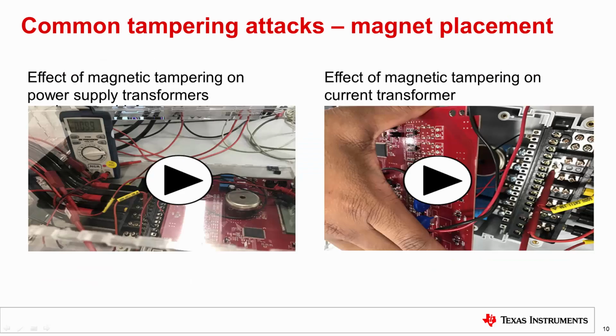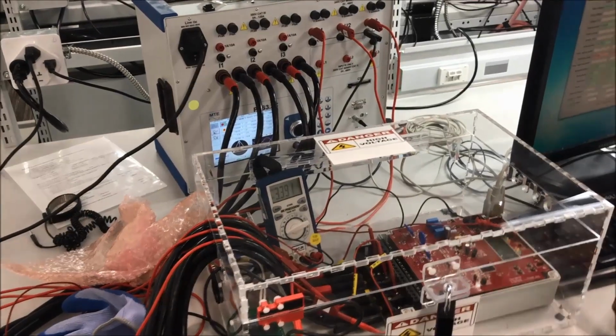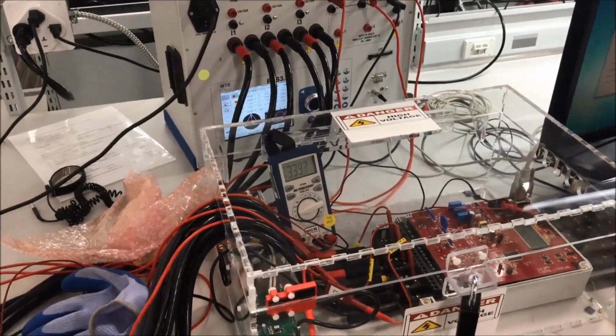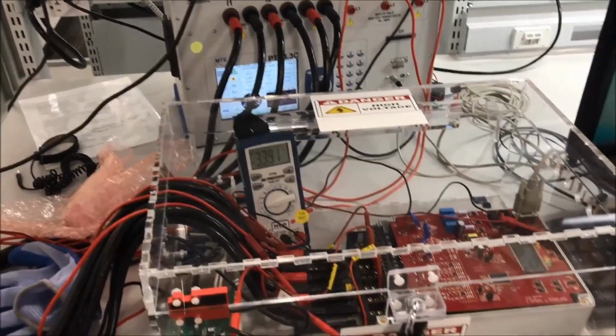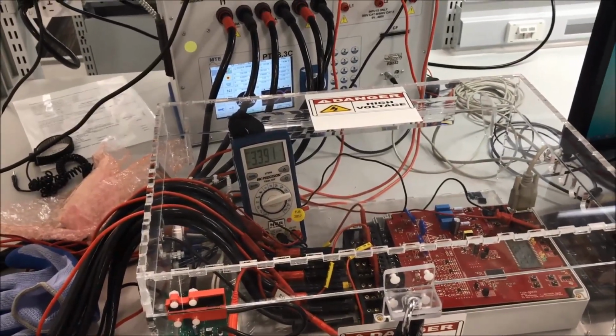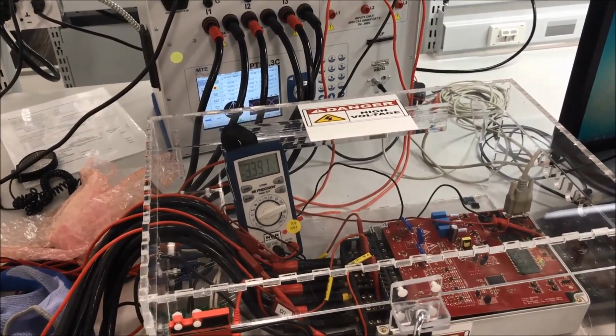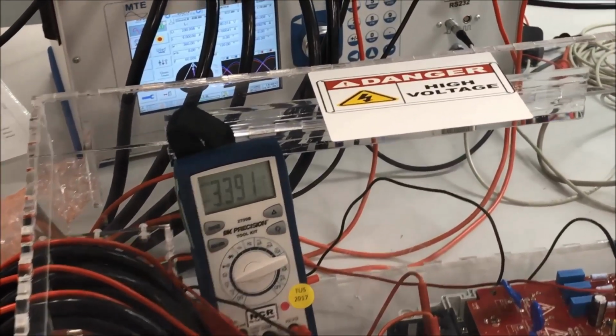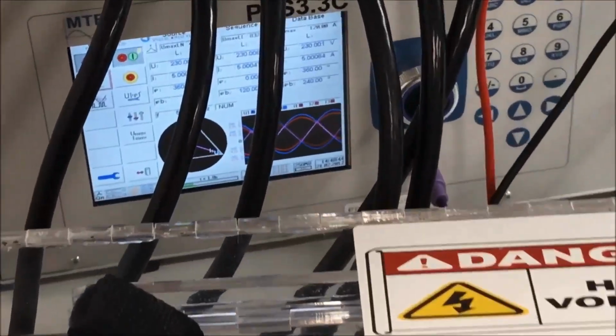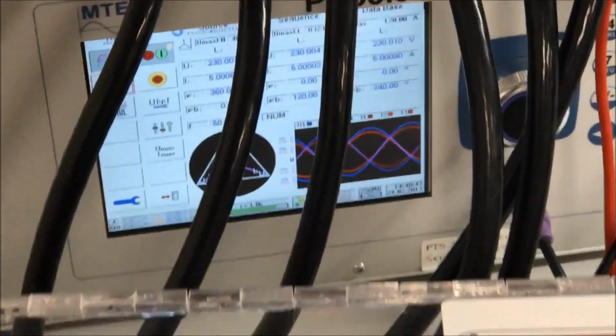One of the most common ways someone tries to tamper with a meter is to apply a magnet on it. This magnet affects transformers and power supplies, as well as current transformer current sensors. This video shows how a magnet could affect a ferrite core transformer in a power supply. To demonstrate this, we measured the output voltage of the power supply. Here we see that it is 3.391 volts when each phase has 230 volts applied to it.